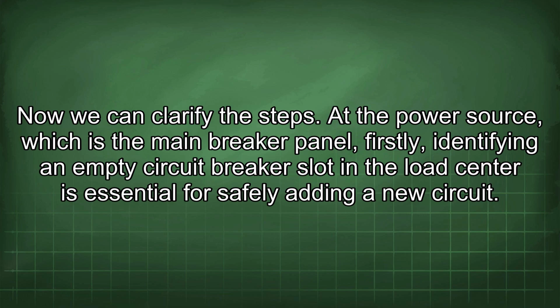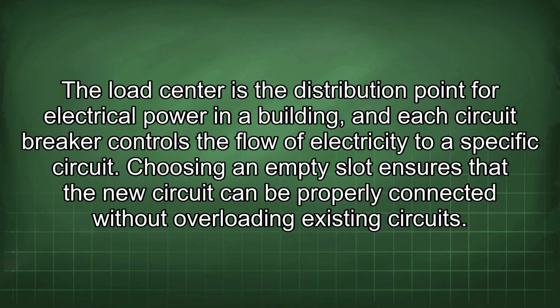Now we can clarify the steps. At the power source, which is the main breaker panel, firstly, identifying an empty circuit breaker slot in the load center is essential for safely adding a new circuit. The load center is the distribution point for electrical power in a building, and each circuit breaker controls the flow of electricity to a specific circuit. Choosing an empty slot ensures that the new circuit can be properly connected without overloading existing circuits.